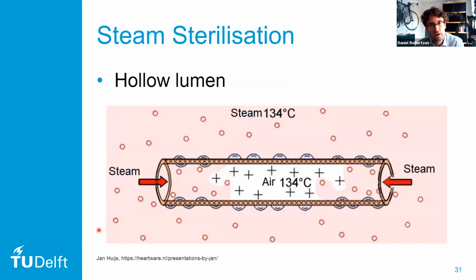The problem with this is that if you have steam that slowly comes down, the steam will try to get into the lumen from both sides, and it will trap air in the middle. The problem with that is that the moisture in the steam makes the sterilization much more efficient. In steam of 134 degrees Celsius, it takes 3 to 5 minutes to perform sterilization. If you have just dry air at the same temperature, it takes about 2 hours to perform proper sterilization. So we need this vacuum in our autoclaves if we want to sterilize the laparoscopic instruments.